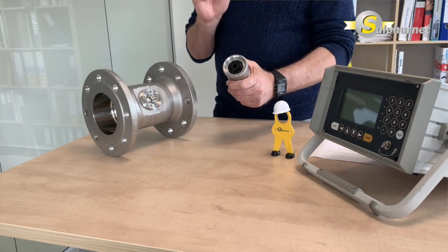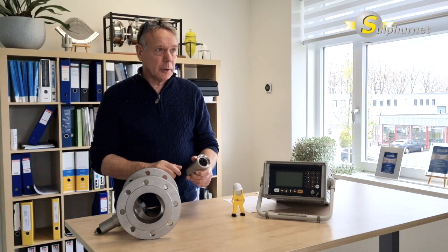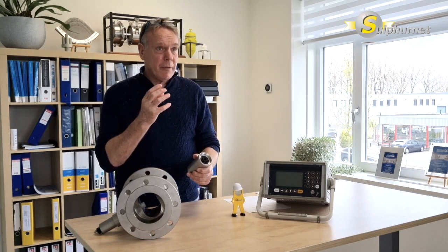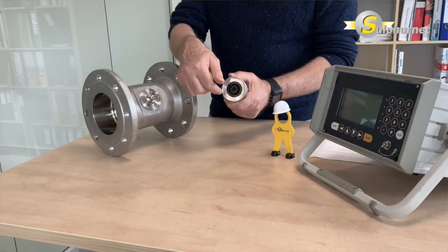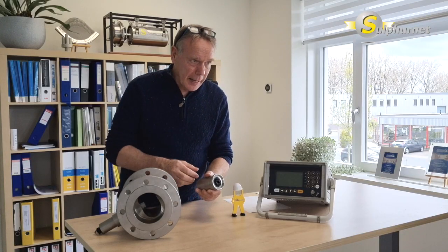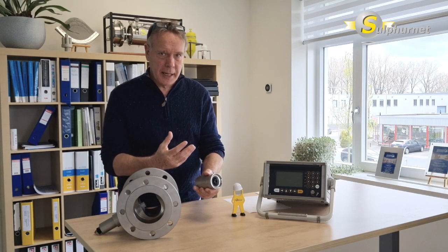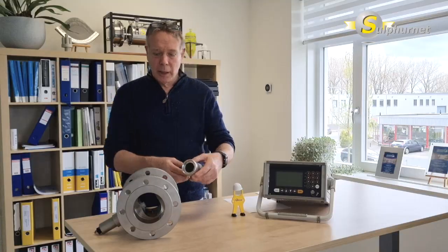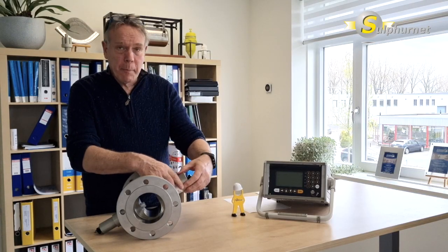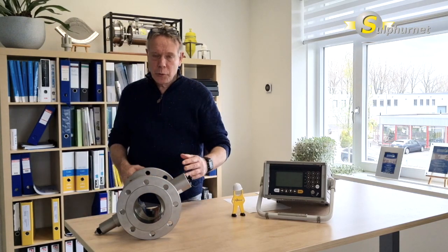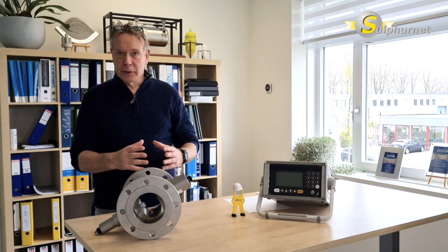When all the light is going straight and there is no bypass, then the light in the middle is highest. But if you have particles, then you have scattering, and then the scattering is going to the side eyes, and that is measuring the scattered light, and the volume and the amount of scattering light is an indication about how many ashes are in the sulfur at that moment. The cell is installed in the pipeline behind the filter, so you have a continuous flow and continuous measuring of the ash level in the sulfur.